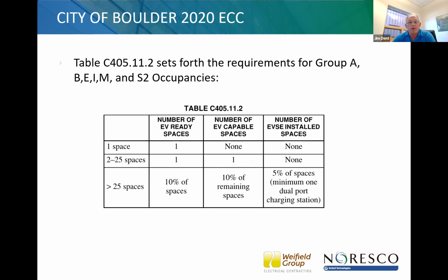So C405.11.2 sets forth the requirements for Group A, B, E, I, M, and S2 occupancies, which is your commercial office buildings. Greater than 25 spaces, it's 10% of the spaces EV ready, 10% EV capable, and then EVSE installed would be 5% of the spaces. Okay, Kevin?